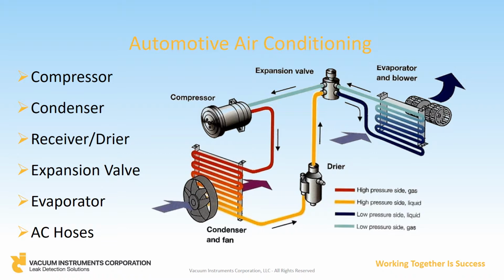The compressor, due to the nature of its dynamic shaft seal, is generally tested to a slightly larger leak rate specification. In either case, these parts are typically tested using a hard vacuum leak test system with helium as the tracer gas. The expansion valve has a much tighter leak rate specification, typically on the order of 10 to the minus 8 cc per second, and would require a hard vacuum leak test system.